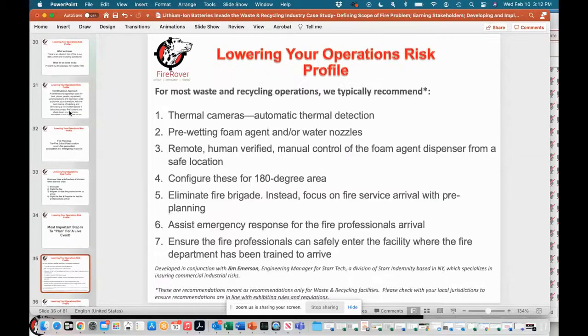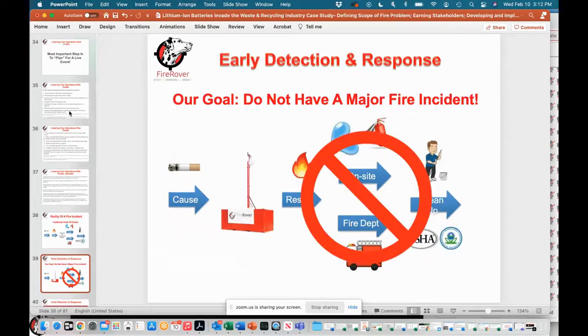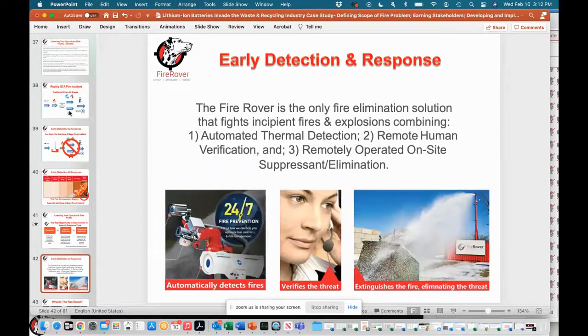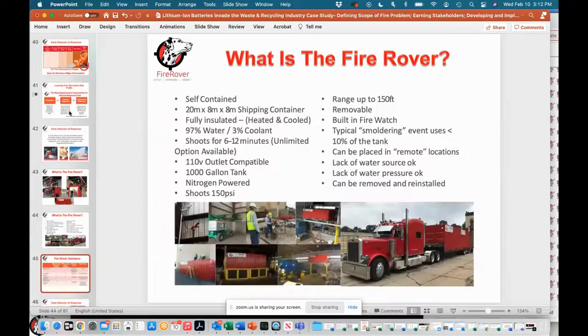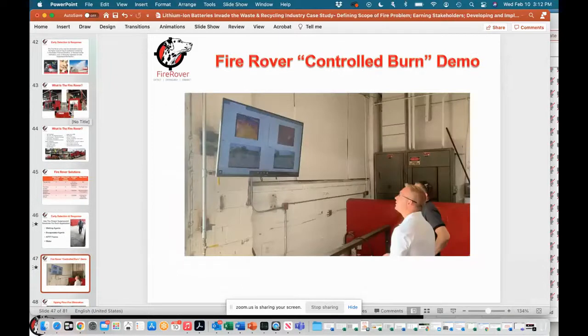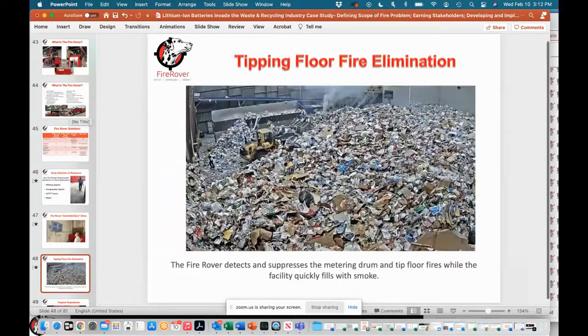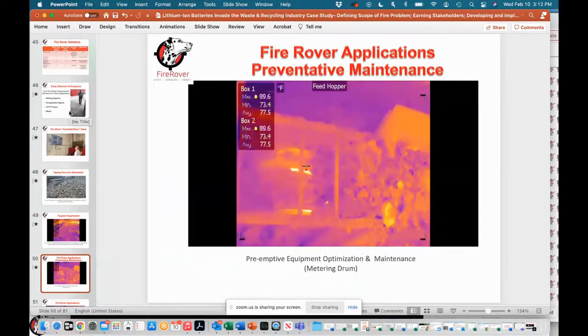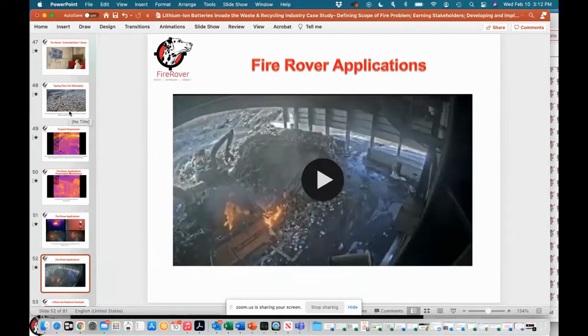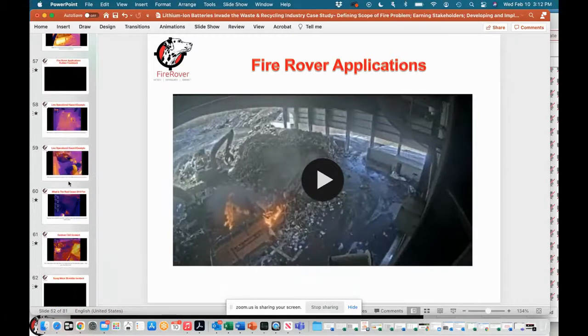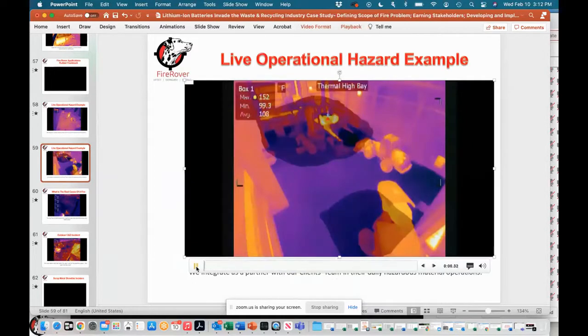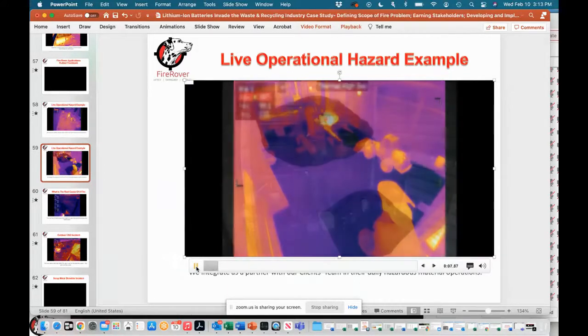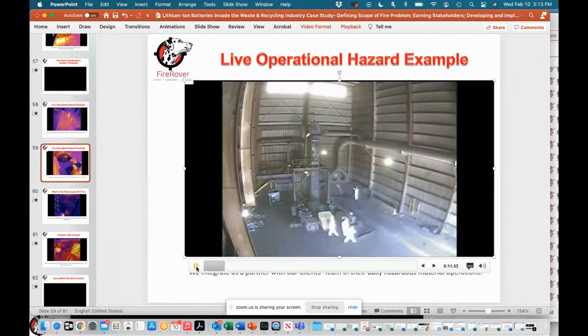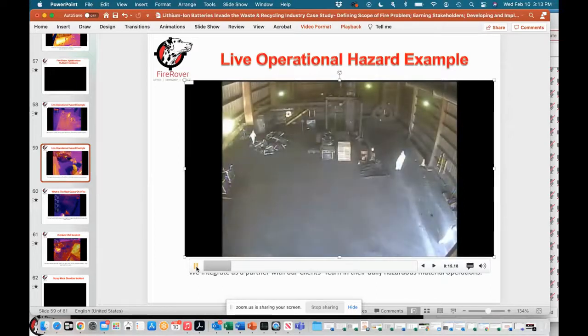That's the key point folks need to consider. With a couple of my customers we've talked about sprinkler systems versus the Fire Rover solution. Since you're monitoring with thermal imaging, compare that to a traditional sprinkler system, even deluge or closed head, which is looking for heat at the ceiling to activate. In most of these facilities you may have a 30 or 40 foot ceiling. Even if you're trying to get temperatures to 130-160 degrees to trip a sensor 40 feet above the fire, what volume of fire do you have before the system even activates?